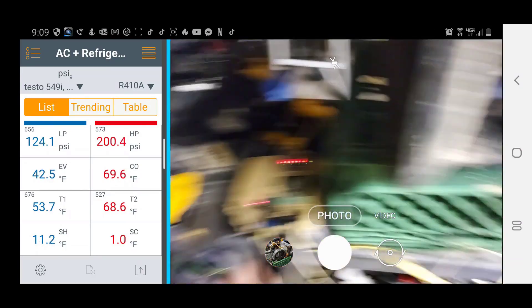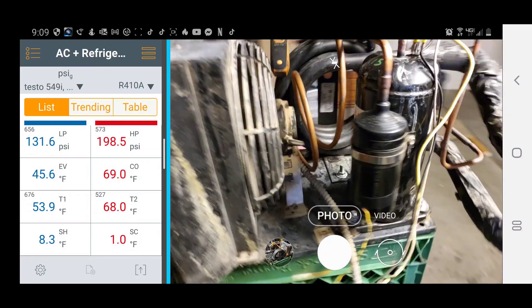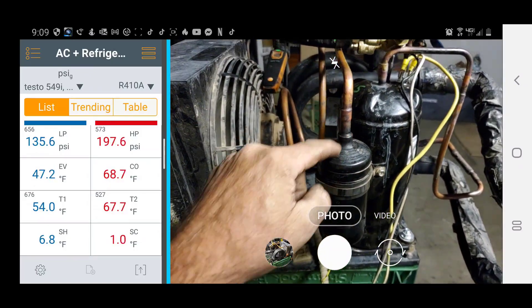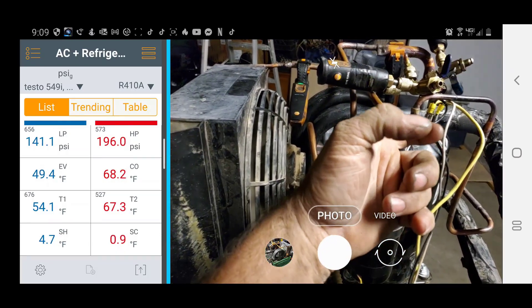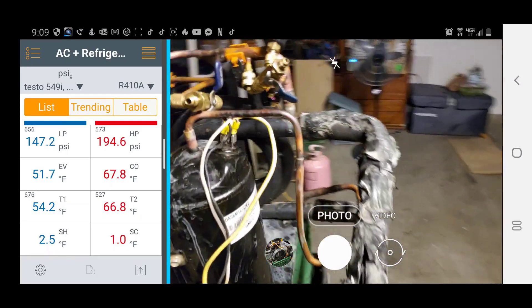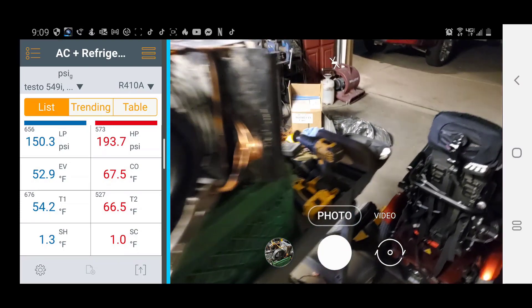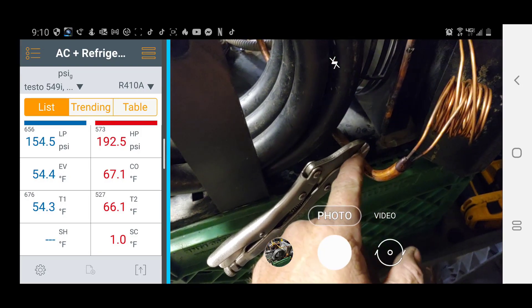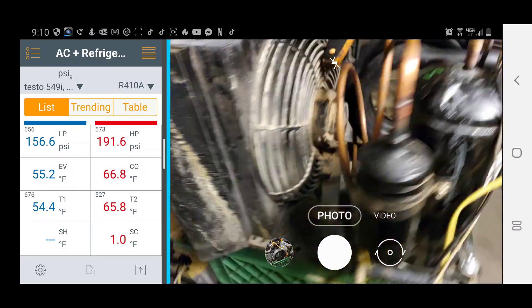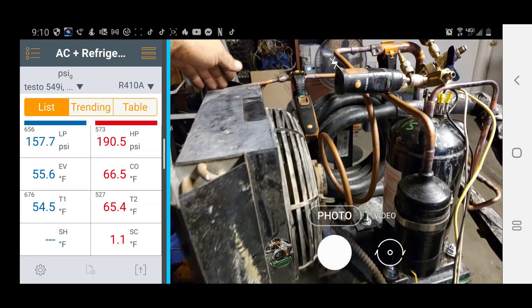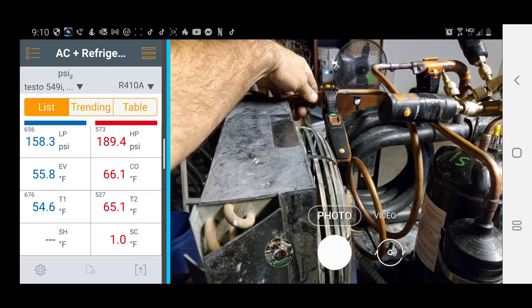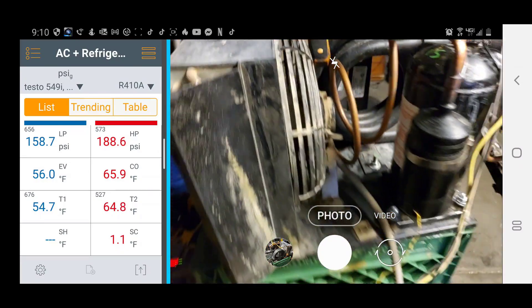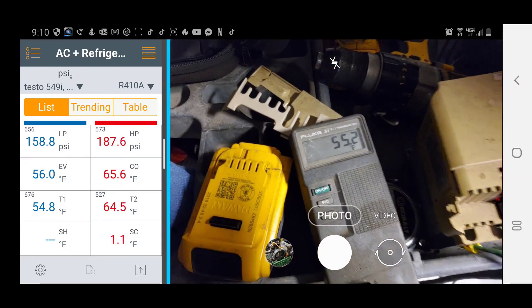So again, some pretty weird thing going on here. I'm taking temperature with this on the bottom of the accumulator here. I'm pretty sure there's a strainer in these—I might have to open it up and take a look. But if there was a restriction here then my suction pressure should be kind of high up here, you would think. It's not. Actually the pressures looked pretty good—it was like 200-something over like 119, 110 going through the capillary tubes. But then I put the pinch-off tool here, I have it way pinched down. And here's the weird thing, and this is a weird phenomenon I've never really figured out: sometimes it's like it's running and it's not even really doing work through the evaporator here. It's not even really dropping the temperature. The suction line is like the same temperature as the room I'm in here. Even when I underfeed it, it still works, and then yet the accumulator will just start frosting up like a mother.